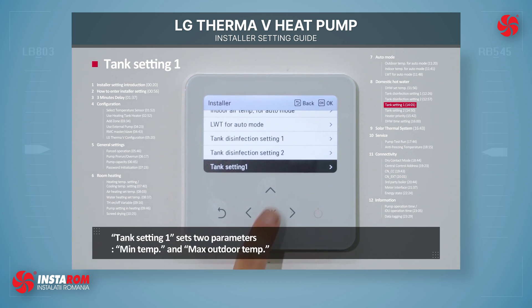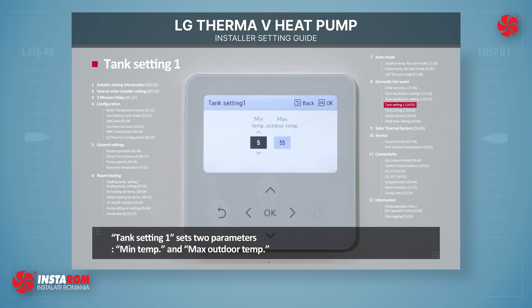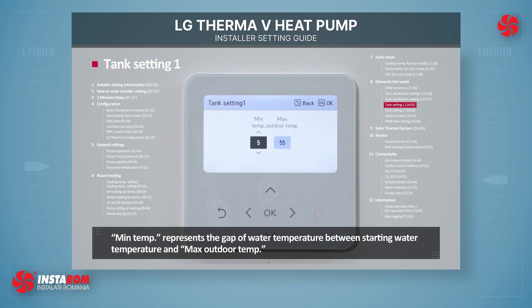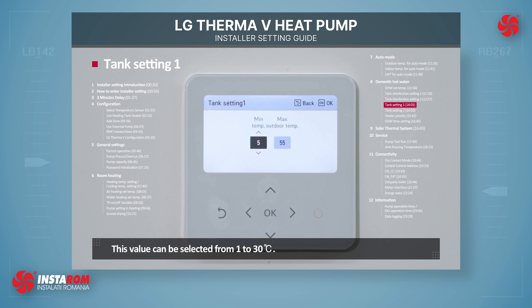Tank setting 1 sets two parameters: minimum temperature and maximum outdoor temperature. Minimum temperature represents the gap of the water temperature between the starting water temperature and the maximum outdoor temperature. This value can be selected from 1 to 30 degrees Celsius.